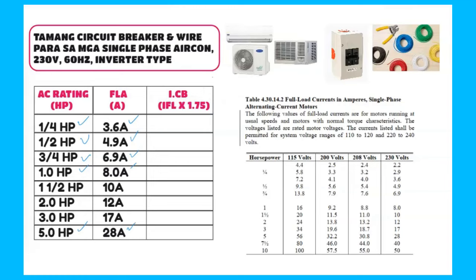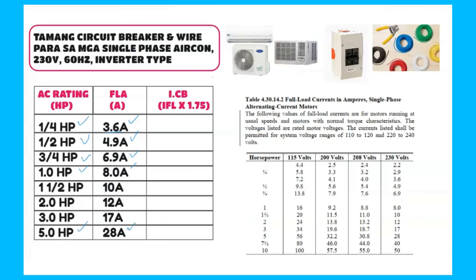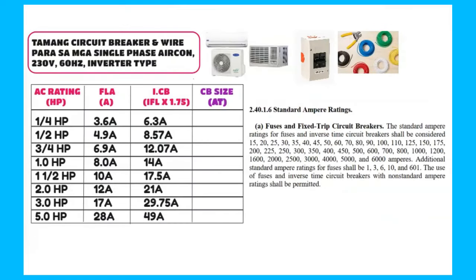1.75. Okay, so to do that, meron yung load ampere natin, that is 3.6. So if i-multiply natin siya to 1.75, that is 3.6 times 1.75, meron tayong makuhang sagot na 6.3. Okay, so and then the next, i-multiply mo lang ulit ito. After multiplying dun sa kanina, itong 3.6 times the 1.75, the answer is 6.3 amperes. So itong 4.9, i-multiply mo to 1.75, ang sagot is 8.57 amperes. Itong 6.9 ampere, i-multiply mo uli dito sa 1.75, ang answer is 12.07.